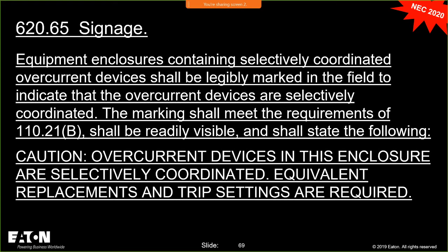So the guys and gals that sit on this code panel recognized that you need to have a marking that says overcurrent devices in this enclosure are selectively coordinated. Equivalent replacements and trip settings are required for that reason. We want to maintain the coordination of that equipment. All right, that's all I have to say about that.